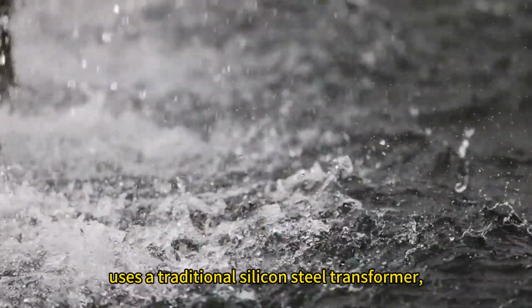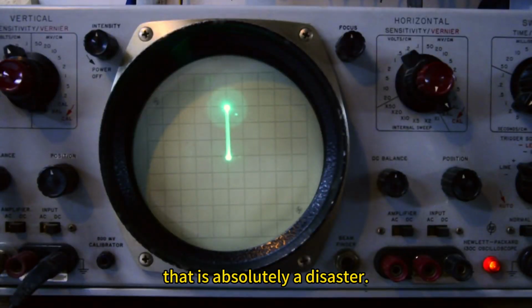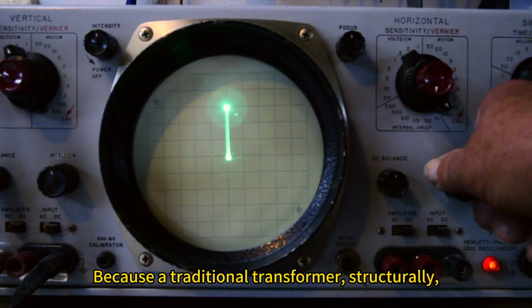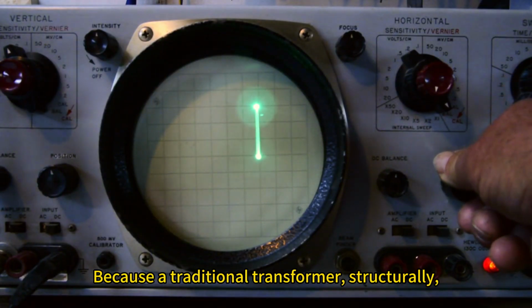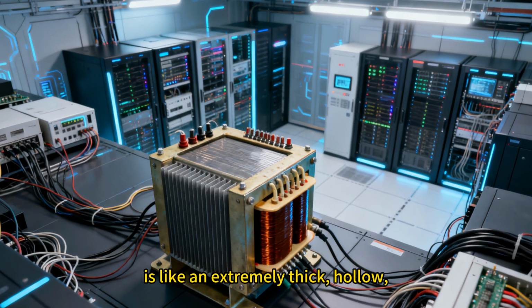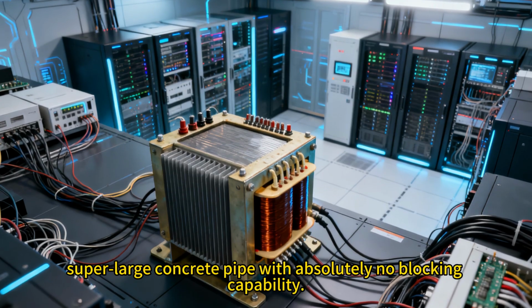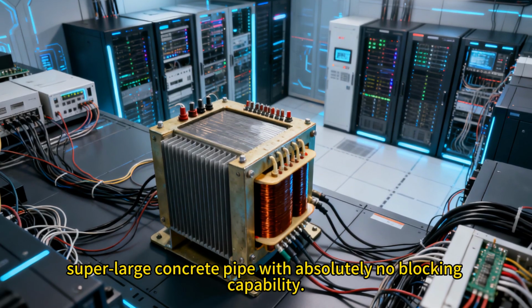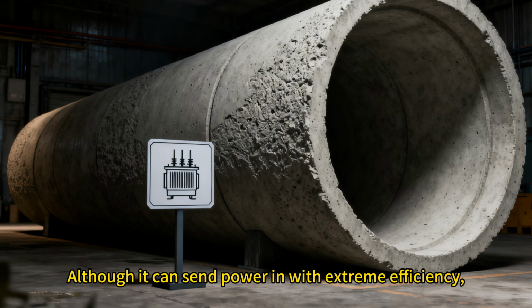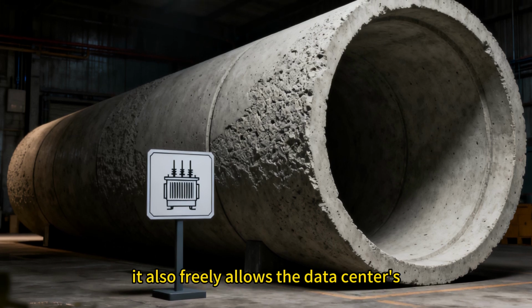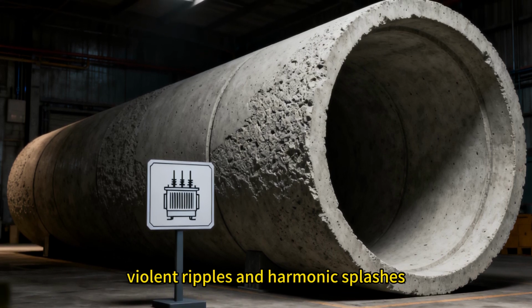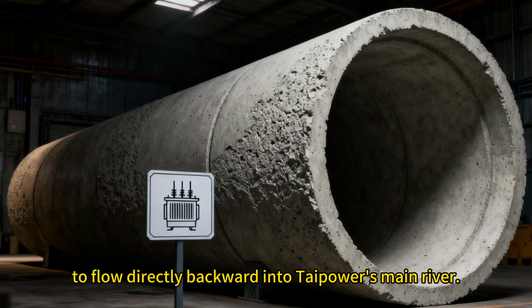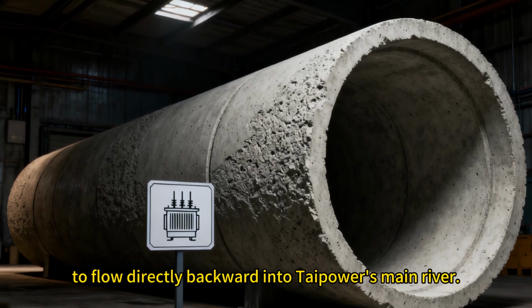If the front end of your AI data center uses a traditional silicon steel transformer, that is absolutely a disaster, because a traditional transformer, structurally, is like an extremely thick, hollow, super large concrete pipe with absolutely no blocking capability. Although it can send power in with extreme efficiency, it also freely allows the data center's violent ripples and harmonic splashes to flow directly backward into Taipower's main river.